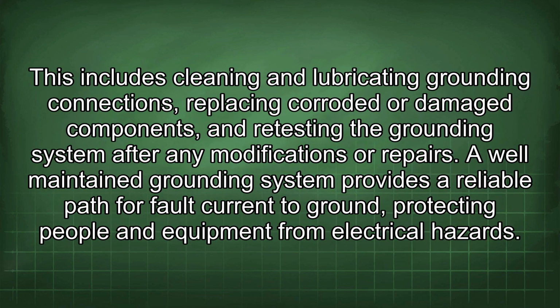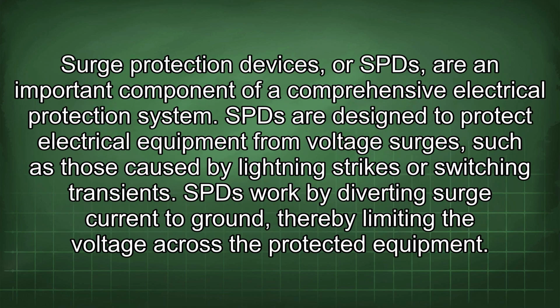This includes cleaning and lubricating grounding connections, replacing corroded or damaged components, and retesting the grounding system after any modifications or repairs. A well-maintained grounding system provides a reliable path for fault current to ground, protecting people and equipment from electrical hazards. Surge protection devices, or SPDs, are an important component of a comprehensive electrical protection system. SPDs are designed to protect electrical equipment from voltage surges, such as those caused by lightning strikes or switching transients. SPDs work by diverting surge current to ground, thereby limiting the voltage across the protected equipment.